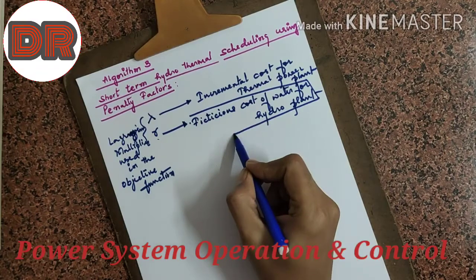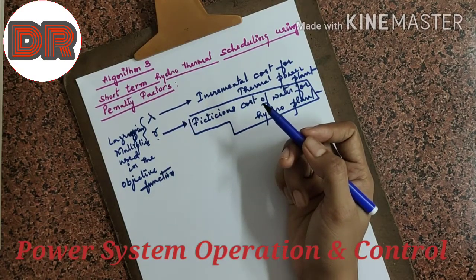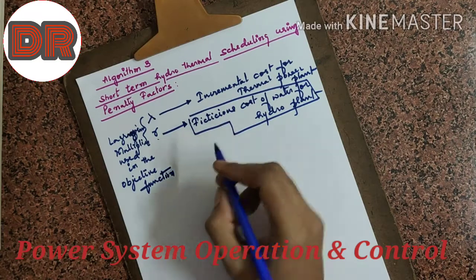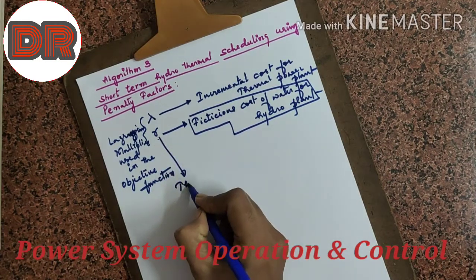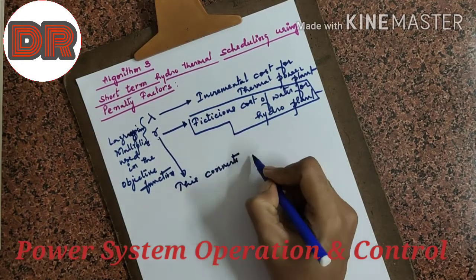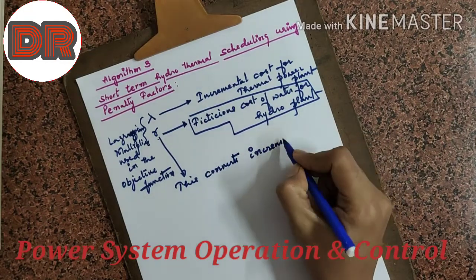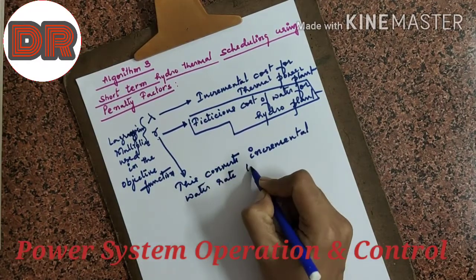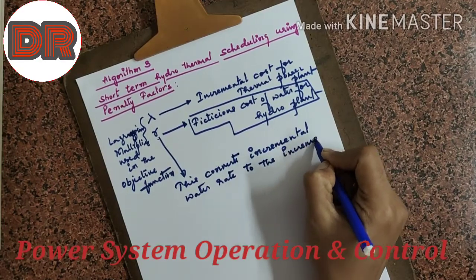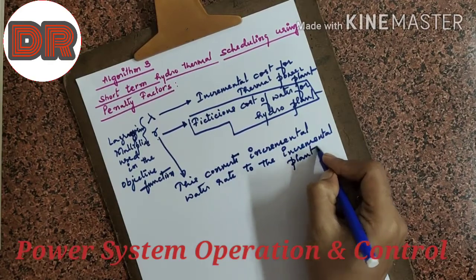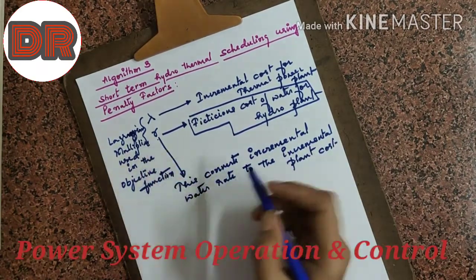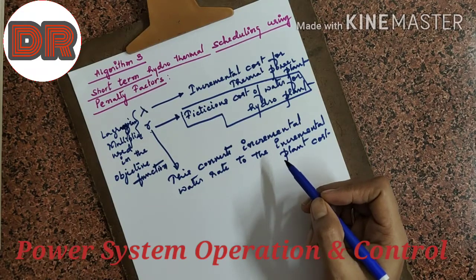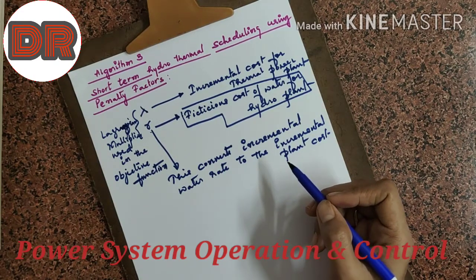We have to make use of this cost because we want the incremental cost for the hydro plant, that is why we multiplied gamma in the Lagrangian equation. This converts the incremental water rate to the incremental plant cost. Ultimately, the objective function has to be in incremental plant cost.